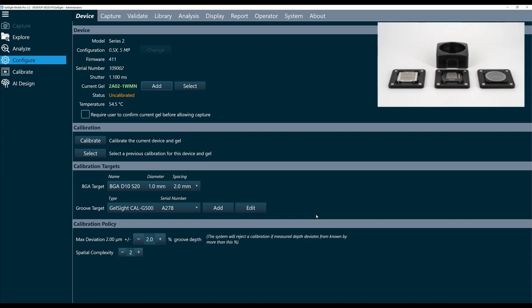Next, we're going to make sure the calibration targets that are configured in the software match the calibration targets that we have physically. For the GelSight Mobile Series 2 half-X system, the BGA target, or ball grid array, should be set to D10S20, and you'll find that printed on the target itself. Next, we're going to confirm that the groove target, serial number, and depth match the groove target that we have on hand.